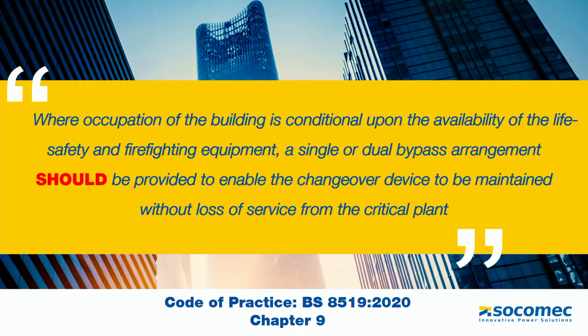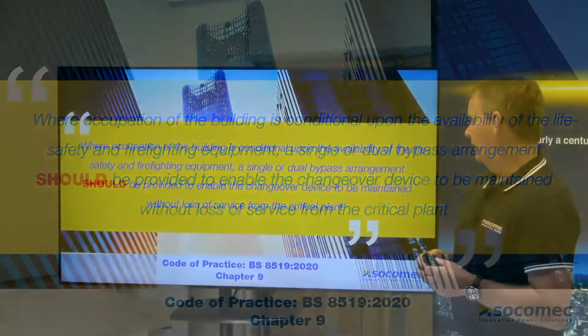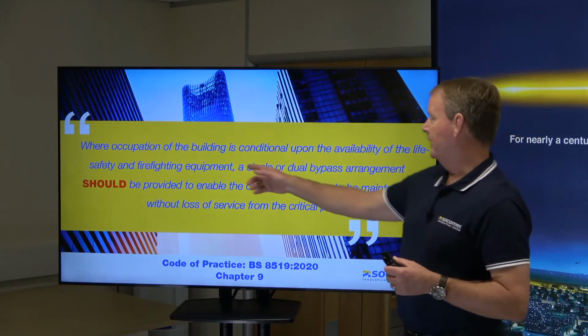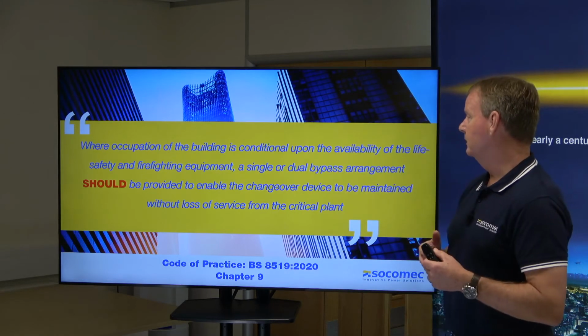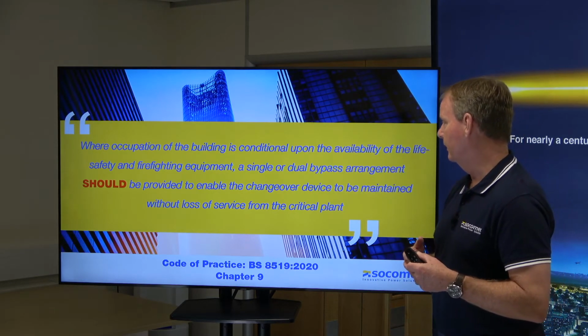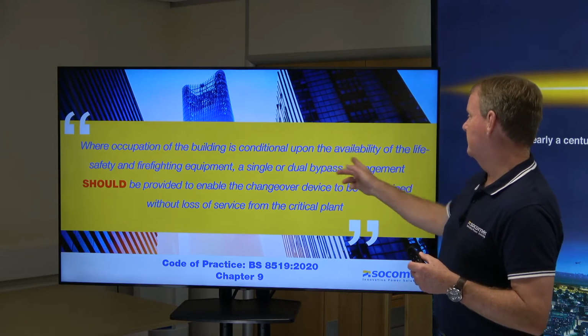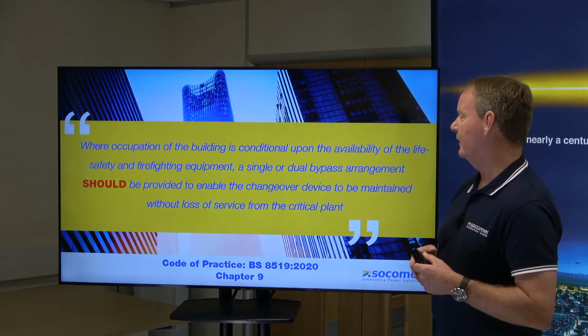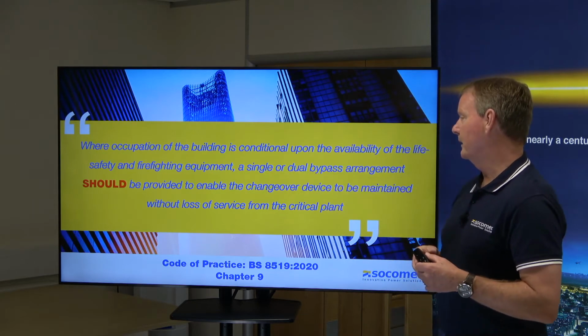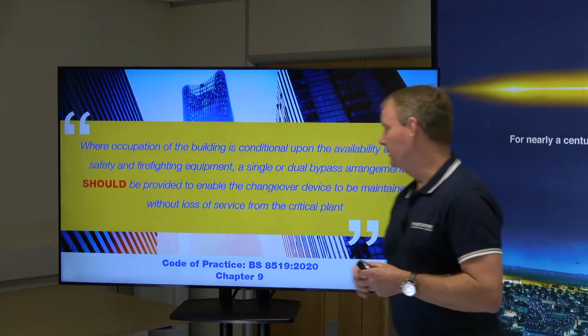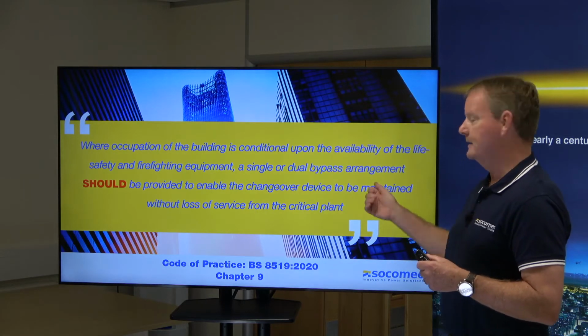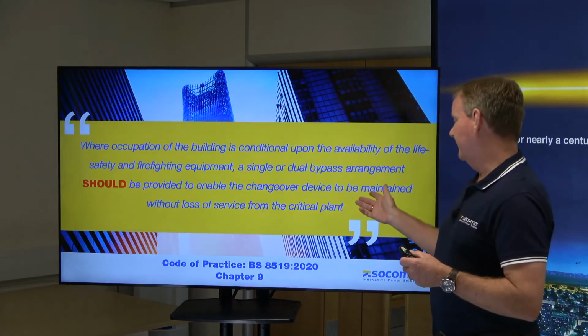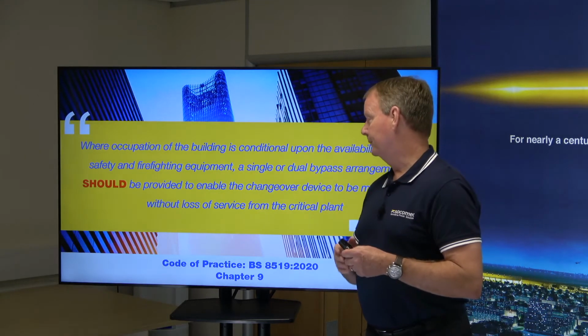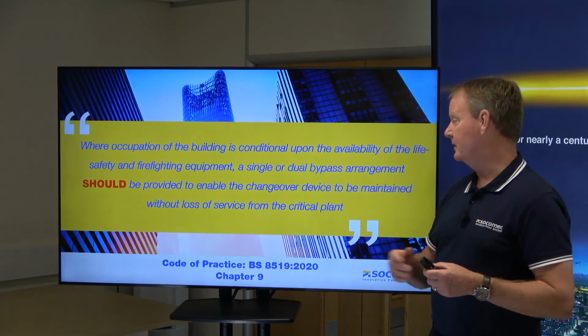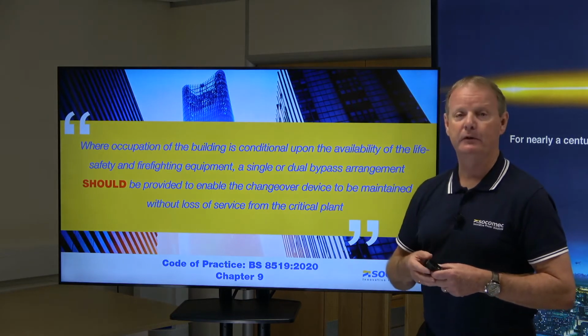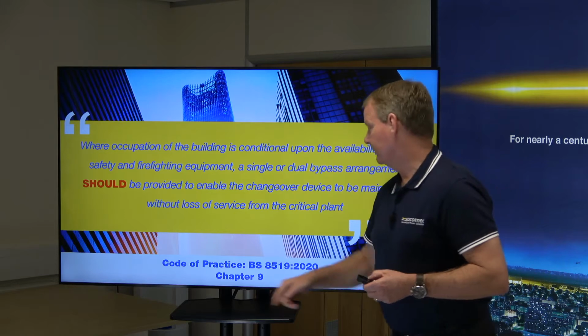So one of the other main points out of the BS 8519-2020 is that when an occupation of the building, obviously for people, normally residential, high-rise or office blocks, is conditional upon the availability of life safety and firefighting equipment, a single or dual line bypass should be provided to enable the changeover device to be maintained. What it means is basically the ATS can have preventive maintenance, or if it is taken out of service, there will be no loss of service for the critical plant, and that's in Chapter 9 also.